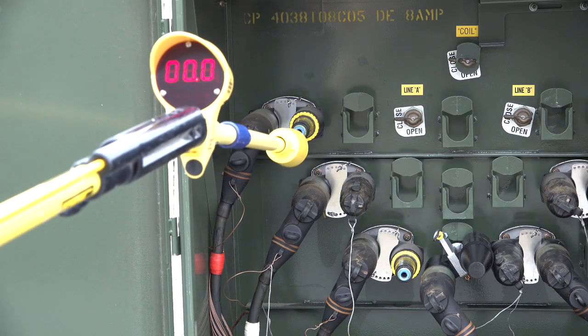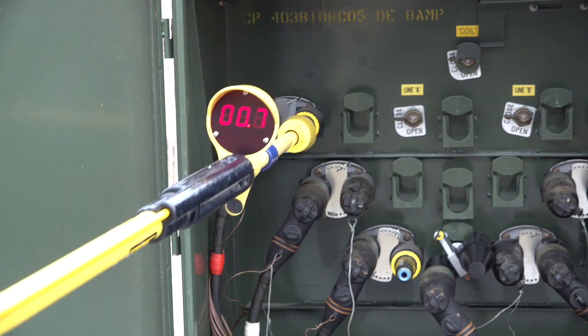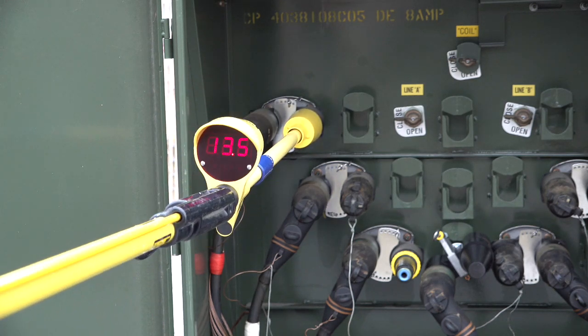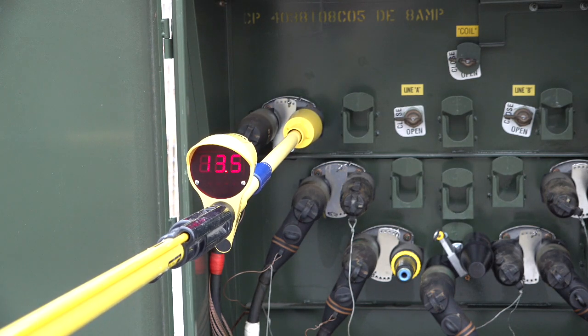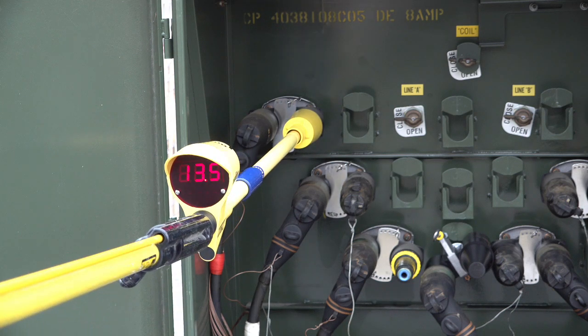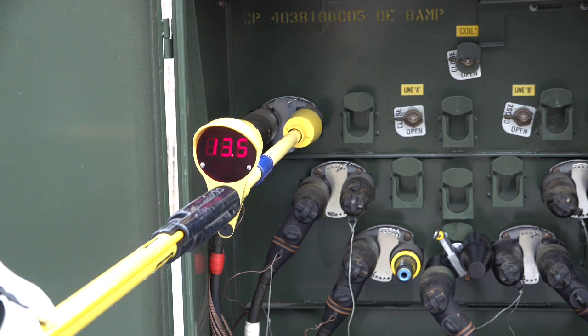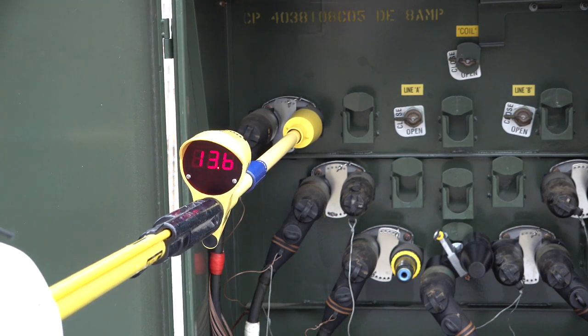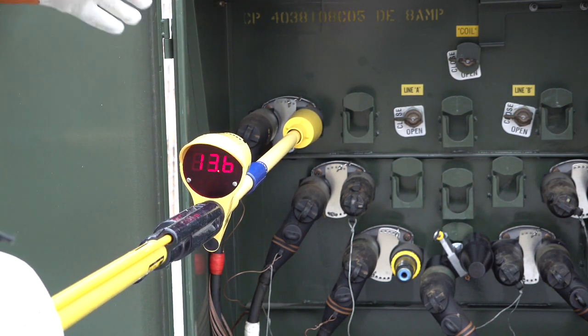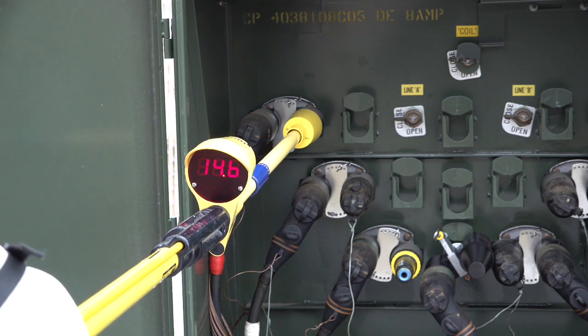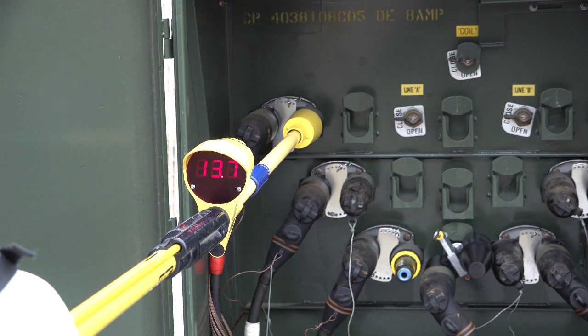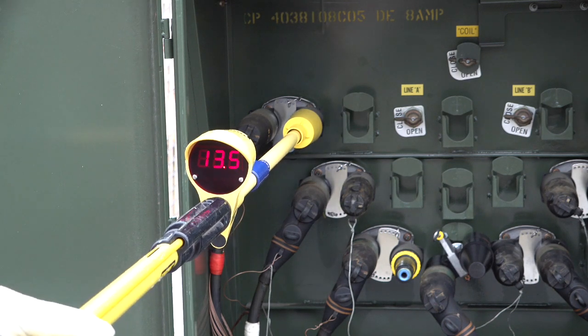So let's go back to our example on the upper left bushing adapter where our reading was high. If you recall, the reading was 16.3 kV. Now the reading is 13.5 kV, or roughly 4% off the true RMS reading of 14 kV we took earlier with the PD25. Notice the distances now are much better to the top of the meter and to the side of the meter. My glove and body is still a ground plane to the meter, so it still adversely affects the display.